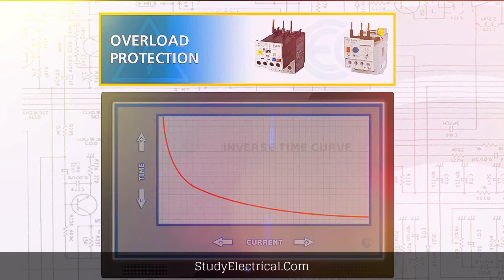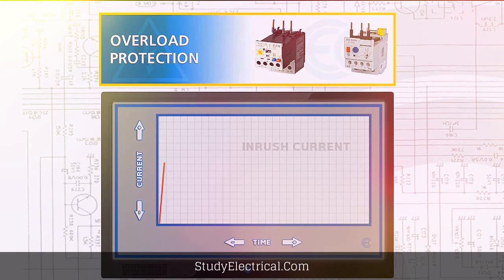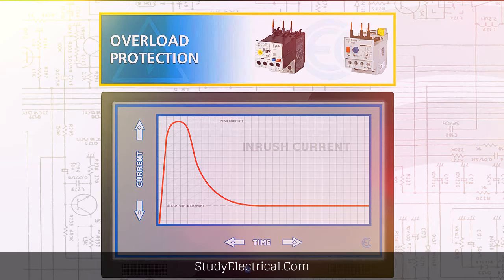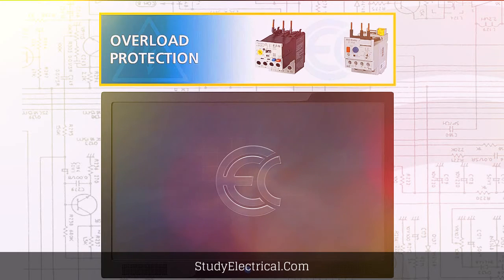For example, some equipment may create inrush currents as it starts up. These inrush currents typically last only a few seconds and rarely cause a problem. Overload relays are used in a motor circuit to protect motors from damage caused by prolonged periods of overcurrent.